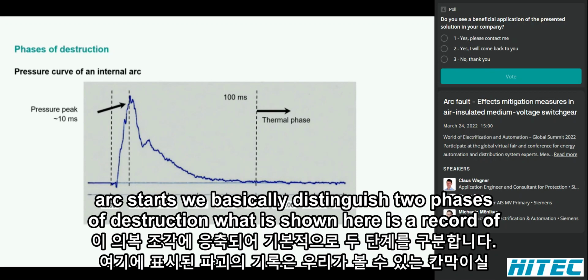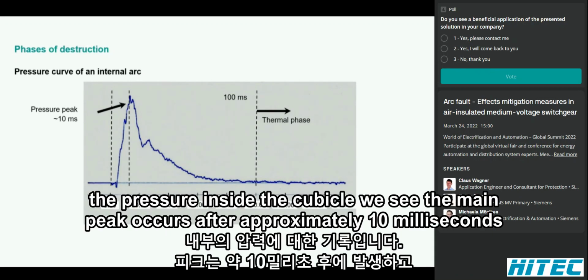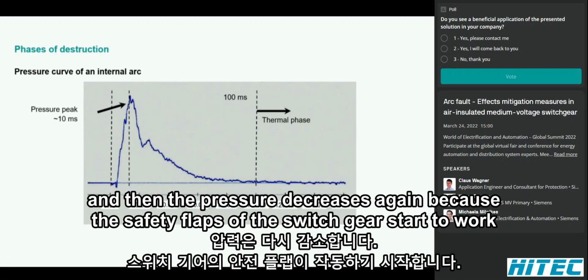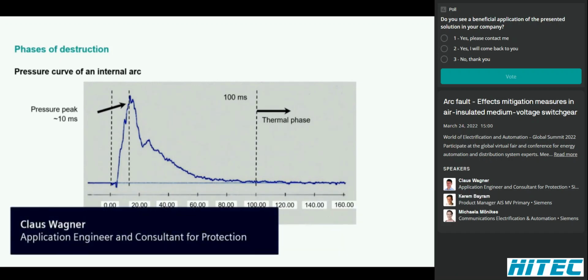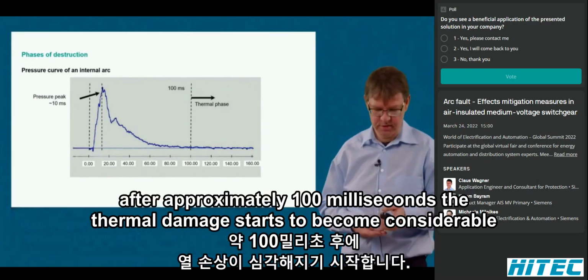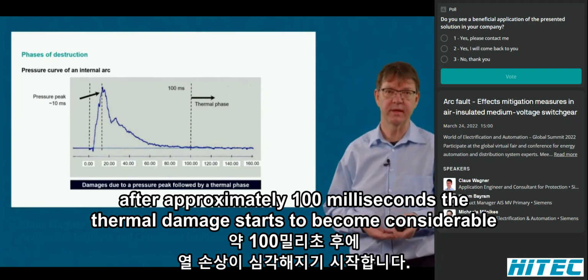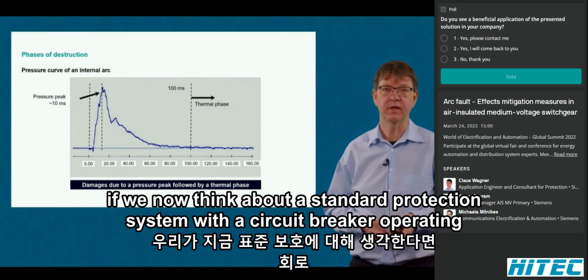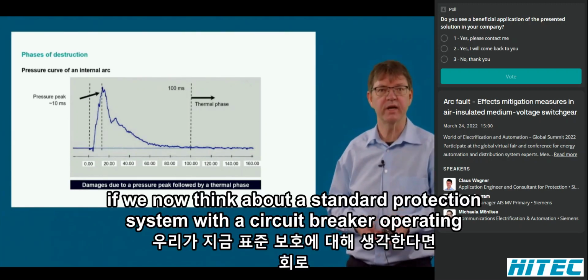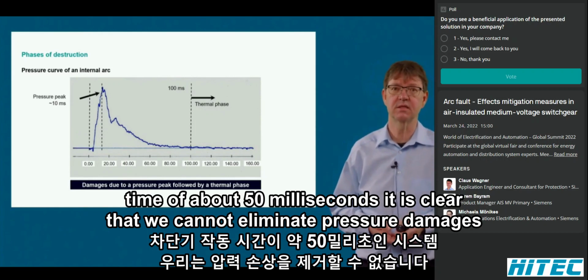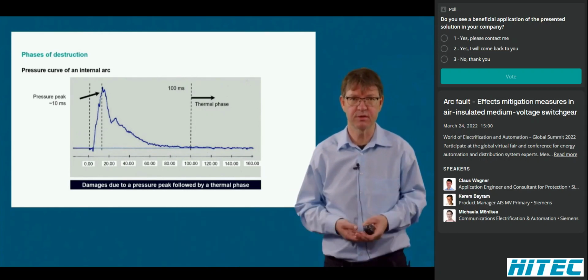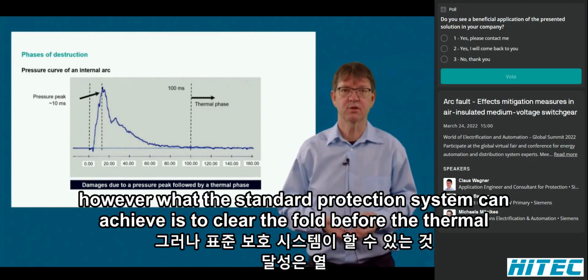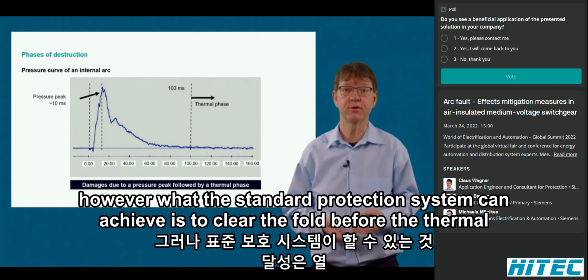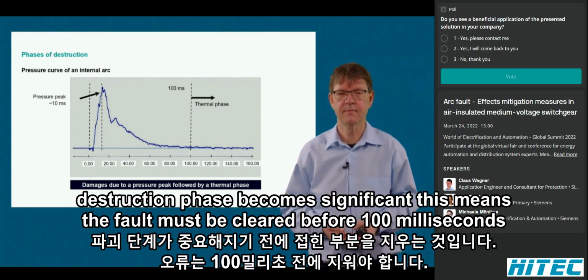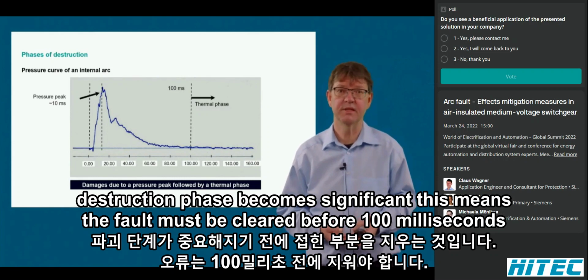What is shown here is a record of the pressure inside the cubicle. We see the main peak occurs after approximately 10 milliseconds, and then the pressure decreases again because the safety flaps of the switchgear start to work. After approximately 100 milliseconds, the thermal damage starts to become considerable. If we now think about a standard protection system with a circuit breaker operating time of about 50 milliseconds, it is clear that we cannot eliminate pressure damages. However, what the standard protection system can achieve is to clear the fault before the thermal destruction phase becomes significant. This means the fault must be cleared before 100 milliseconds.